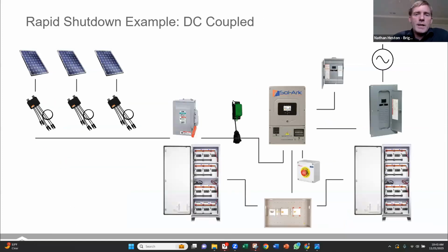So for a rapid shutdown device, here's an example where you can see a rapid shutdown button built into a DC connected system. These are optimizers here on the solar array. That's coming through a disconnect. But this device here is responsible for transmitting that signal. And that's the transmitter of the keep alive signal. As long as this rapid shutdown button is in the normally open position, the inverter will keep powering that keep alive signal coming from the transmitter. And if you push the rapid shutdown button, what ends up happening is it kills the keep alive signal. Killing that keep alive signal turns these optimizers off and turns the panels off at the panel level.